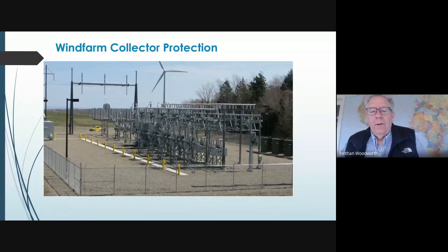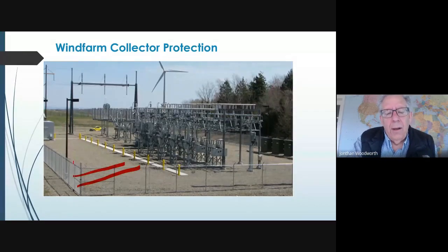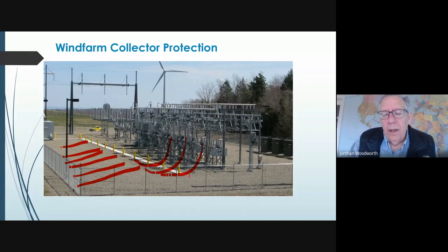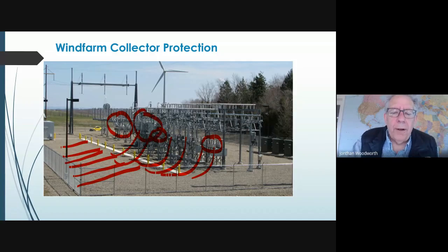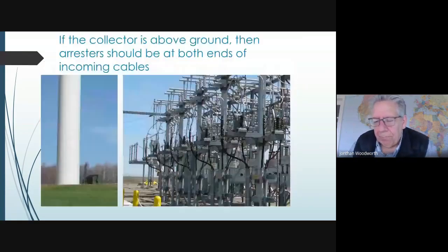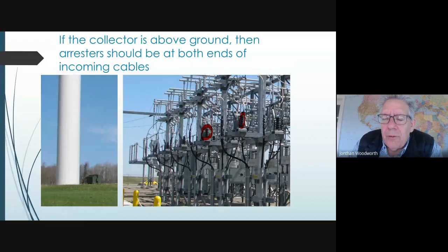Another common location for arrestors is in wind farms, or any substation actually. In wind farms, there's usually many underground cables coming in, and they come up to breakers. And each breaker then has a set of arrestors on them, and it gets very complex. Then there's arrestors back here. I don't see the transformer. Transformers are back behind here. So this is what the substation entrance would look like in a wind farm, and there's many arrestors inside these for protection.